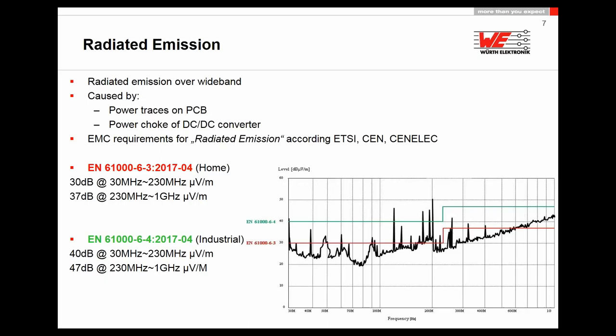The EMC lab will also test for radiated emission in a chamber. For radiated emission, you have two different levels — the home level and the industrial level. Industrial is allowed to be a little more noisy. However, even if you think your device is sold B2B only to commercial customers and not standard home appliances, you still have to meet the home level — because as soon as your device can be operated in an office environment, even an industrial customer's office, it becomes home level.